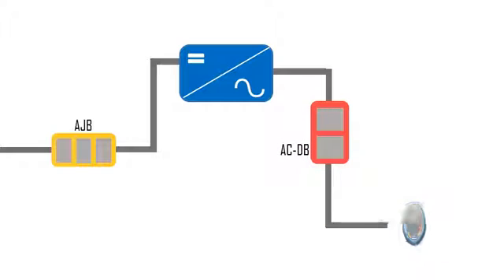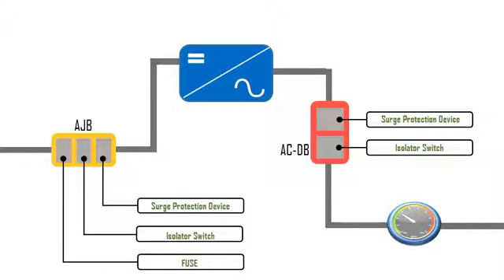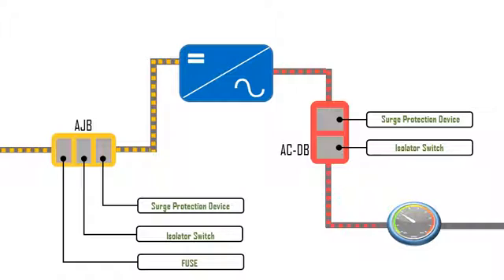The AJB is primarily a box where various solar panels or strings of solar panels connected in series or parallel are conjoined together to produce an output to the inverter. Within the AJB, various protection devices are placed to control any voltage or current surge.